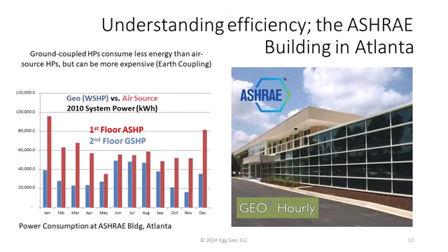So the blue lines here indicate the corrected energy use per square foot for geothermal, and the red lines indicate the corrected energy use per square foot for the air source heat pumps. It's interesting to look at the fact that the geothermal heat pumps are doing their job. This is Atlanta, where the ground temperature is about 65 degrees, so they're doing pretty darn good here, showing that they're more efficient than air source heat pumps in the summertime.